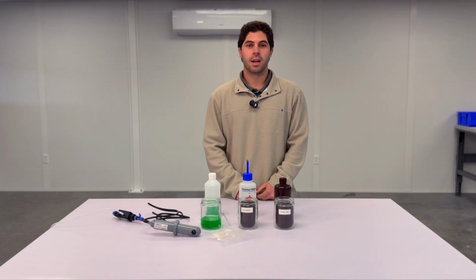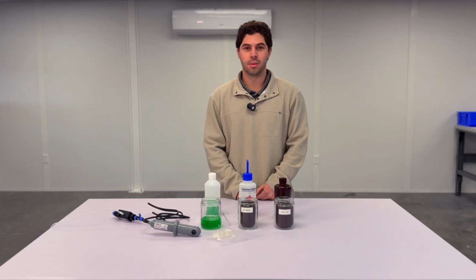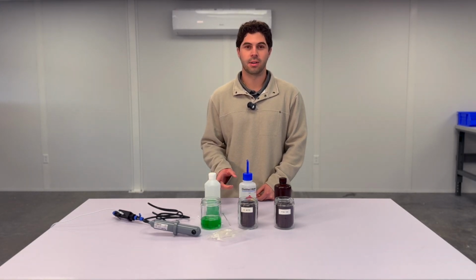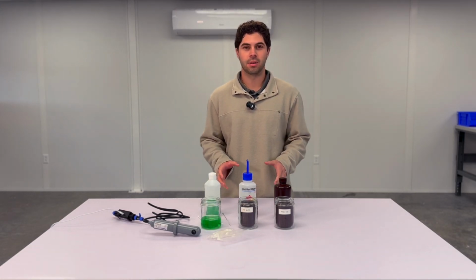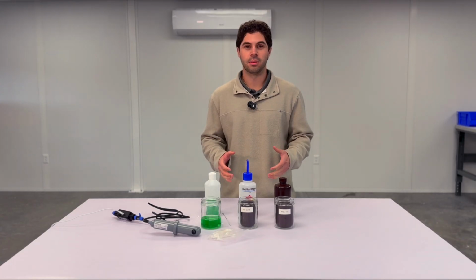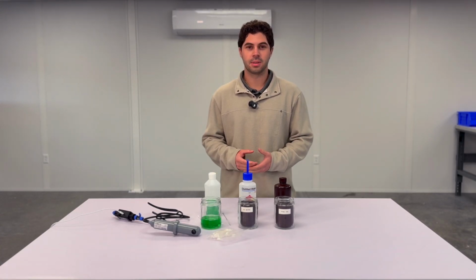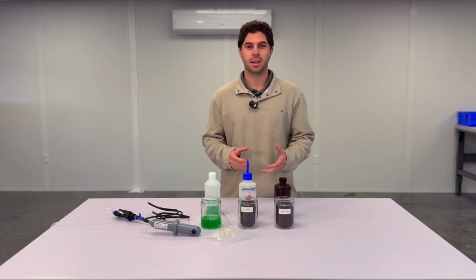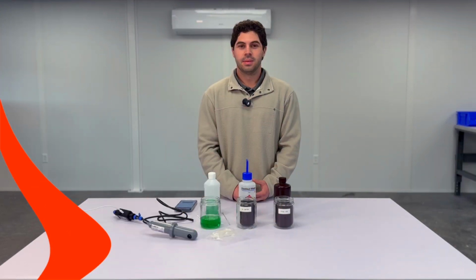Now we're going to go over how to calibrate your ST series probe. We're going to be using an ST500. All the ST series probes follow a similar calibration method, so just follow these steps, but make sure to use your appropriate calibration solution. Now the first step is to perform a zero calibration.